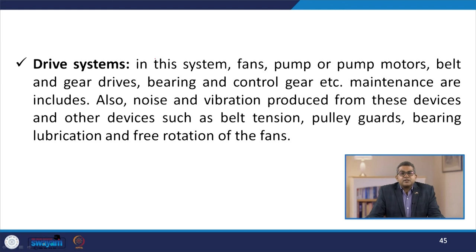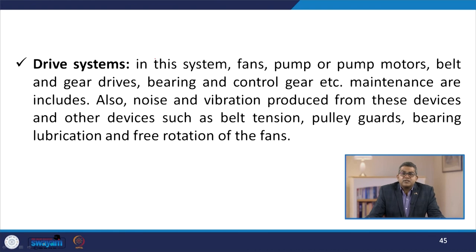Drive systems: this includes maintenance of fan pumps or pump motors, belts, gear drives, bearings, and control gears. Also, noise and vibration produced from these devices should be checked, along with belt tension, pulley guards, bearing lubrication, and free rotation of the fan.